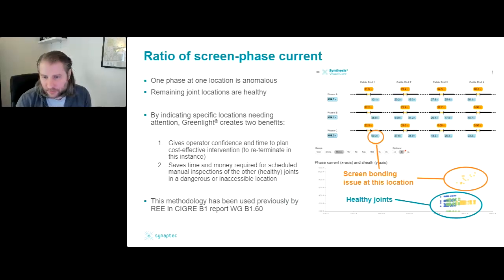So simply by comparing phase current and screen current, or by looking at the ratio of those two numbers, we can immediately see if there's an anomaly, and that's what's shown here. This is real data from a 400 kV cable in Europe, where we find there was an anomaly in one location, and we're able to pinpoint exactly where that is, which joint or which phase of the cable was the guilty one here.